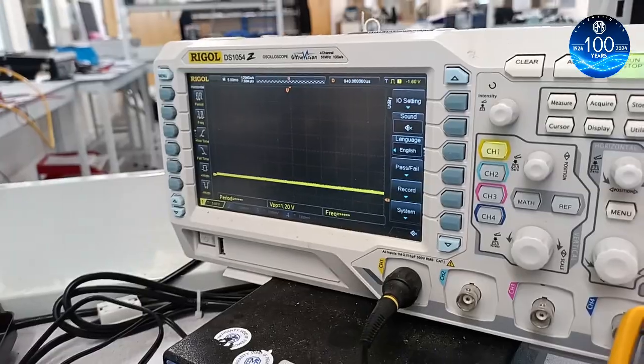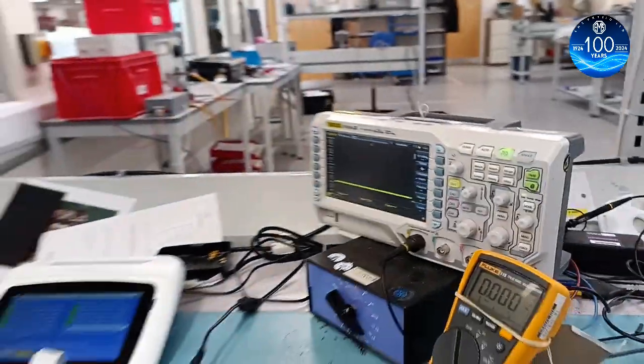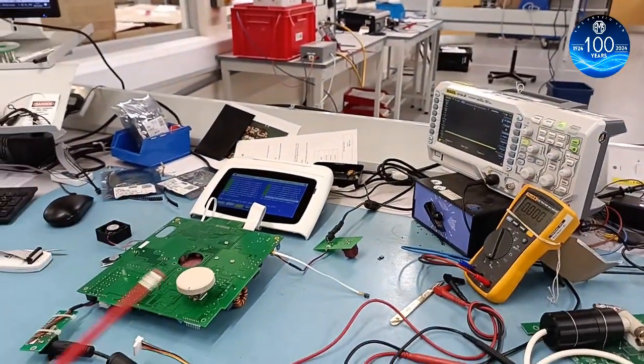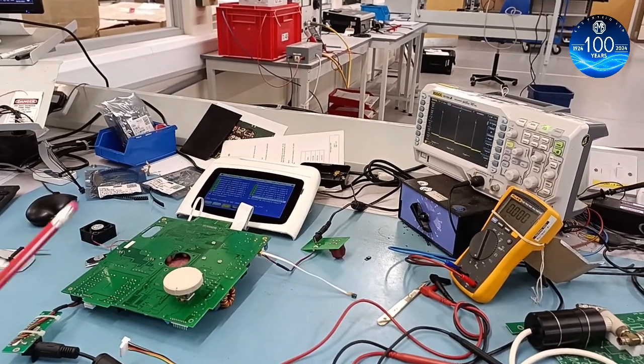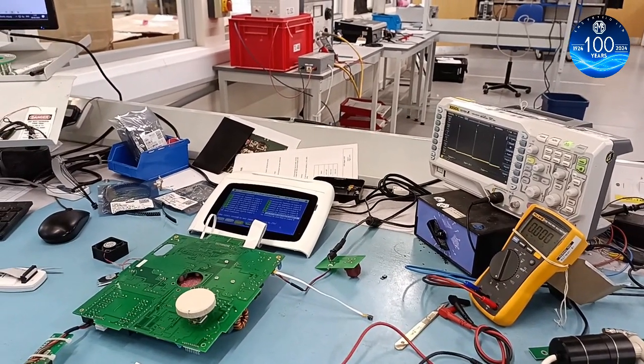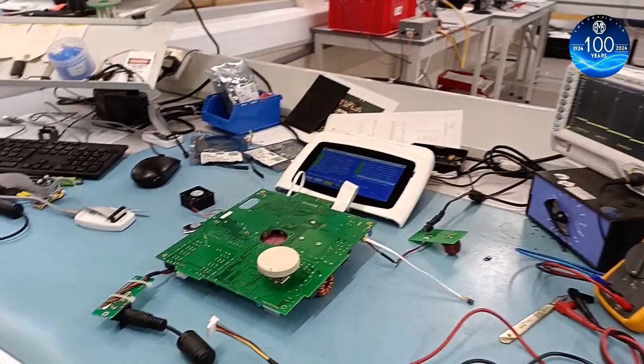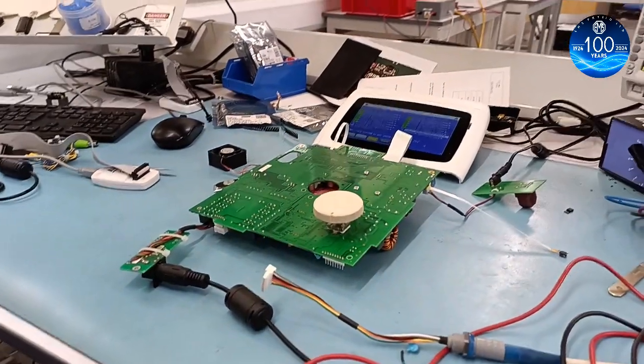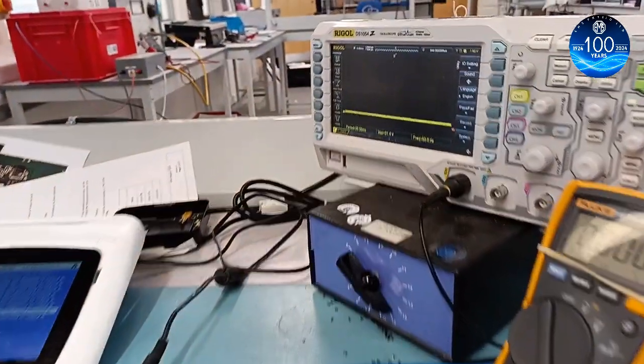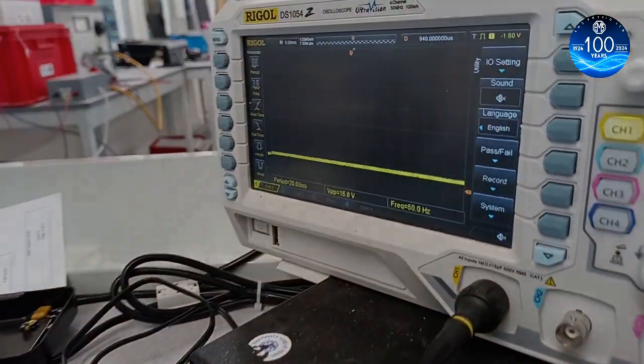This is a semi-automated test that each board goes through, and it will cycle through all of the different waveforms and the different outputs, and the engineer verifying the tests will look at each one independently and check that each output from each waveform is generating the right intensity.